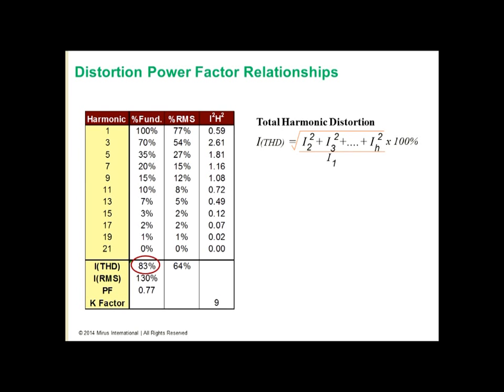So total harmonic distortion is a root sum square calculation, so it is equal to the square root of each harmonic squared. So we have the second order squared plus the third order squared and so on. Take the square root and divide by the fundamental component. So in this example, the particular spectrum has a total harmonic current distortion of 83%. K factor is the sum of all the I squared h squared products. And so we take each of those, we sum them all up, and in this particular example, K factor is 9. So this particular load profile would require a K factor 9 transformer in order for it to be fully loaded.